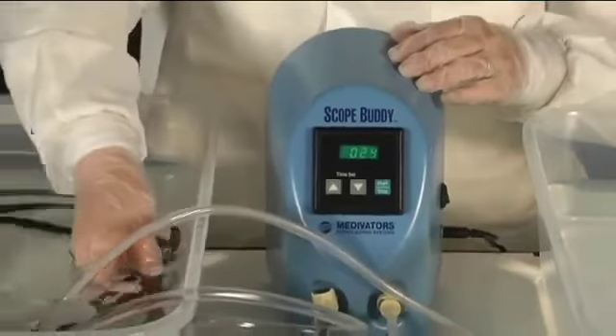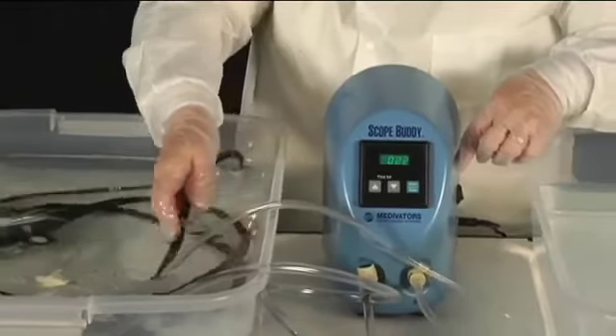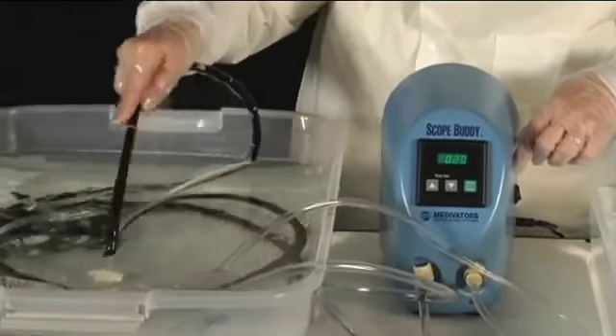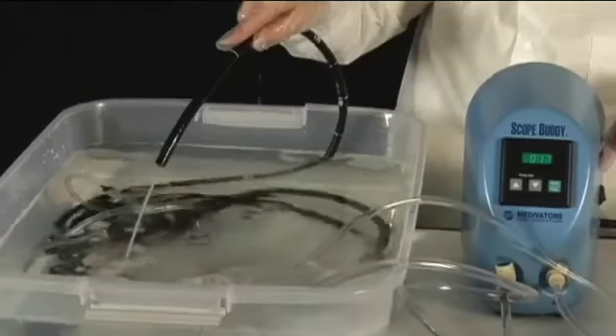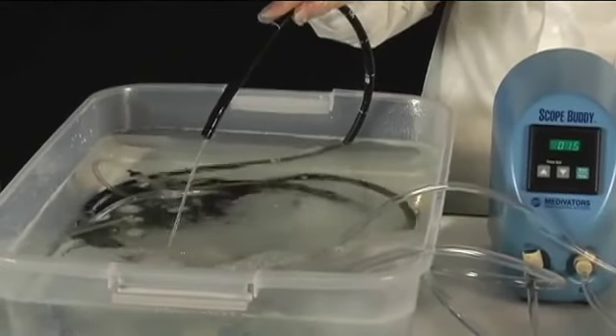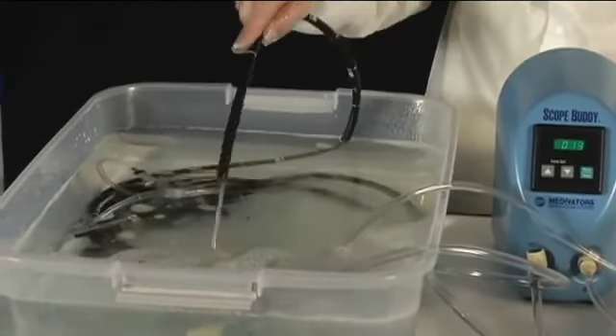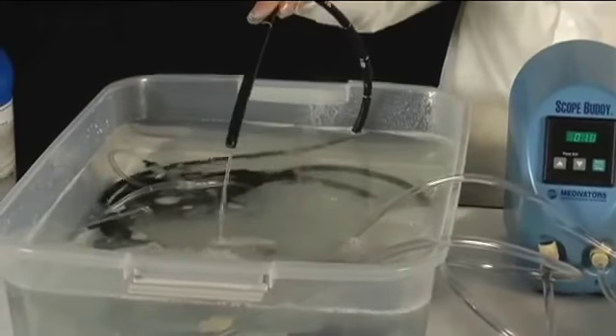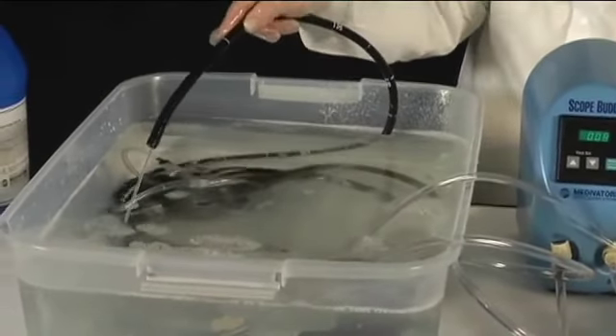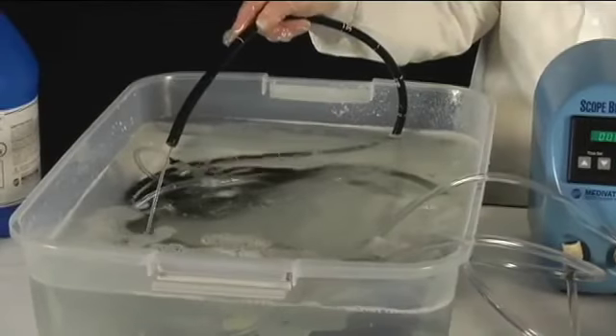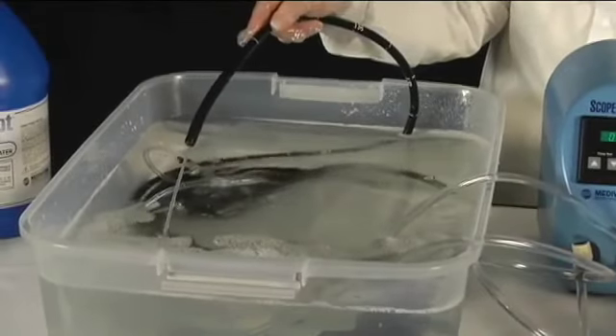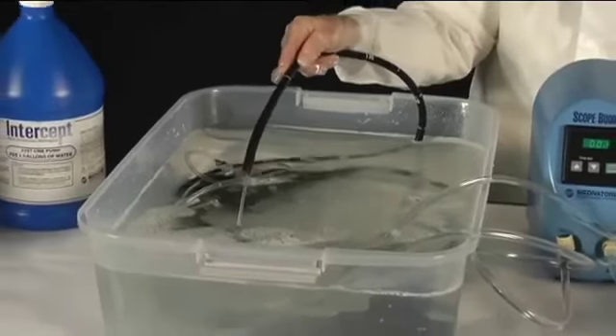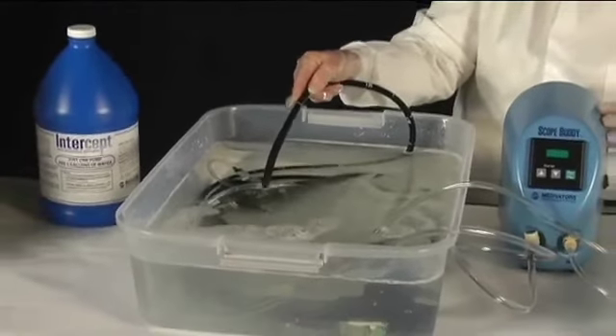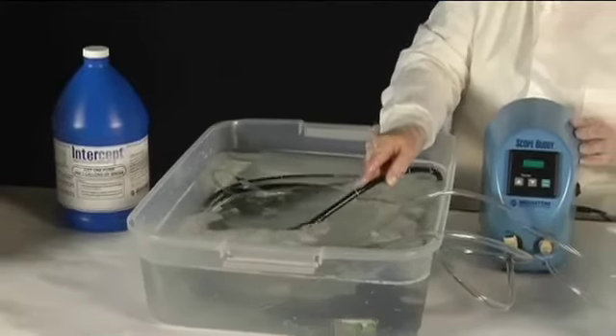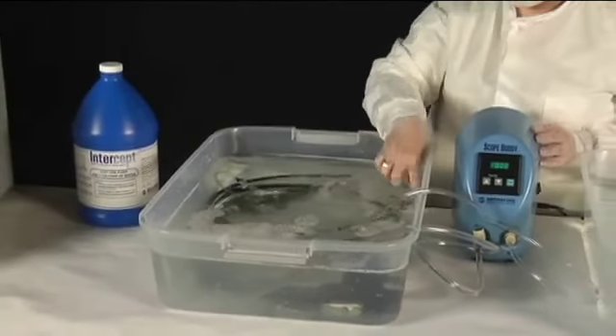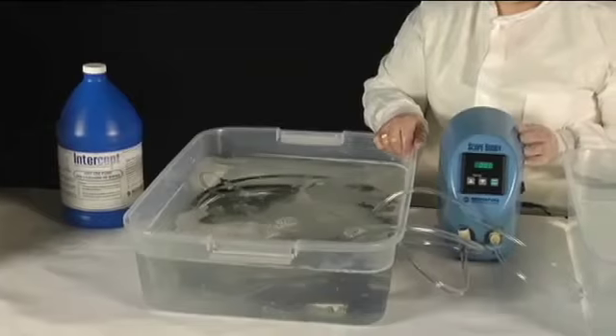Detergent solution will now be drawn up from the sink or clean supply container, pumped through Scope Buddy, and will flow out the endoscope distal tip. Verify solution is exiting all channels of the endoscope distal tip. If fluid fails to come out all channels, then a channel may be blocked and the endoscope may need to be manually brushed and cleaned again. The flushing process will then need to be repeated until flow through the endoscope is verified or the endoscope should be taken out of service.